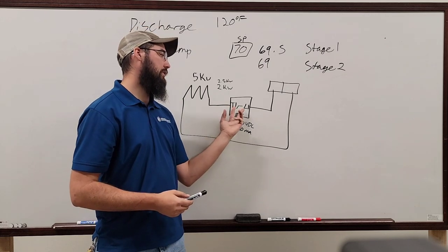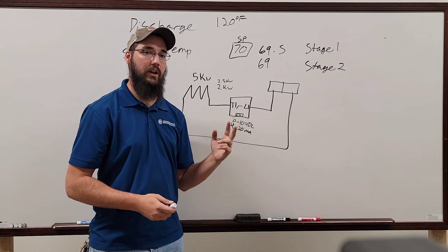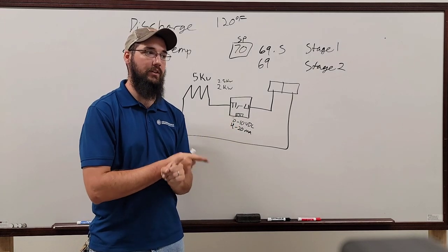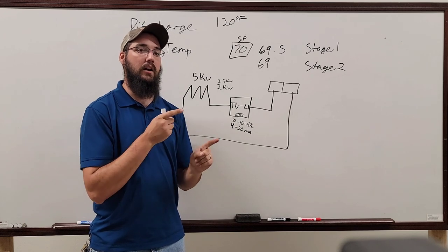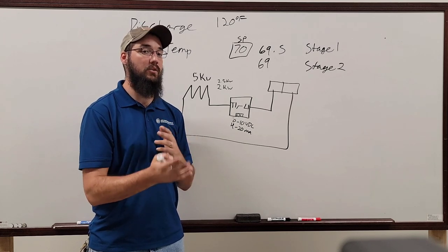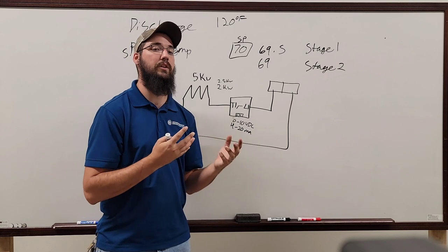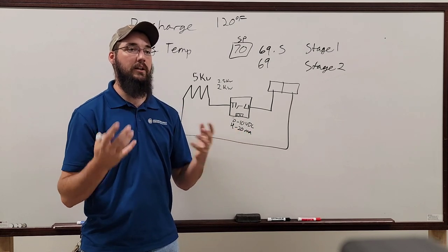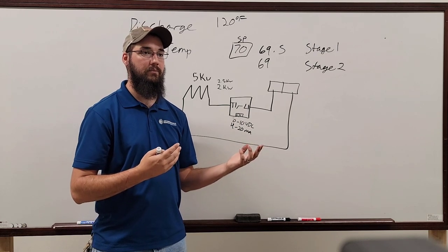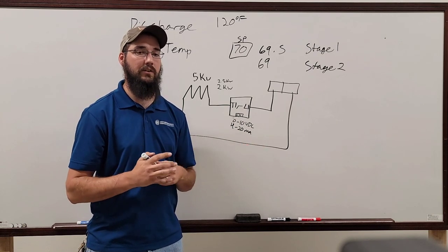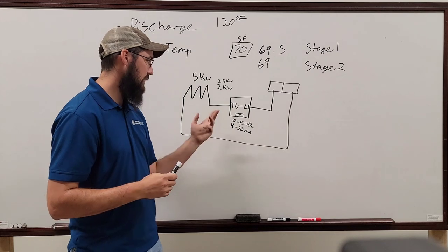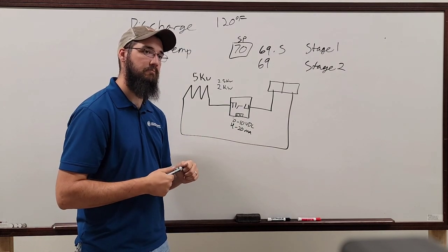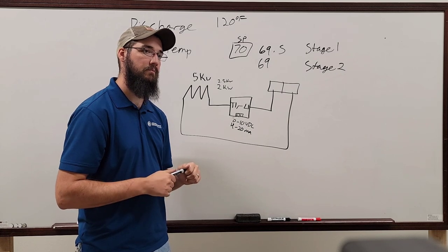Now, you do have the ability to actually test the gates, okay? You would use a diode test to test the gates. But your results of what those readings should be are going to vary relay to relay. Okay, they're not going to be exactly the same. So look up the relay-specific parameters and compare that to the readings.